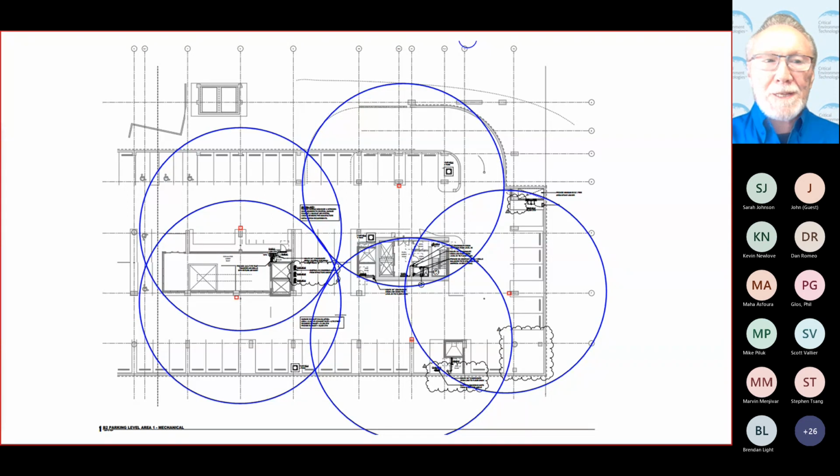So, placing more sensors on the perimeter wall and not relying just on the radius of coverage allows for those sensors to have greater monitoring effect of the full ambient atmosphere within that envelope that you're trying to monitor. So as opposed to placing your sensors 100 feet apart, maybe dropping that back to 60 feet apart so that you've got a few more sensors around the perimeter walls. And we all know that a thermostat on a perimeter wall works fine. So gas sensors, a little closer spaced around that perimeter wall, and the fact that the ambient atmosphere is in constant motion will provide fairly good coverage, even though you can't get them in towards the interior.